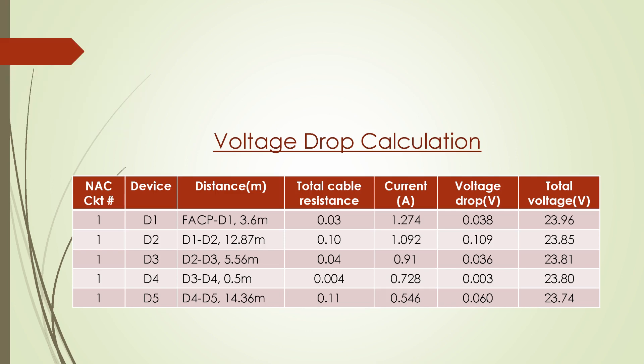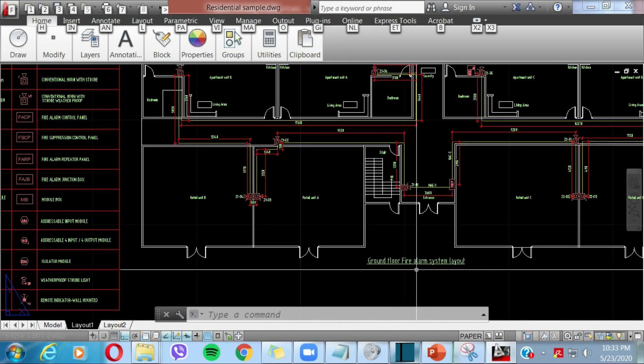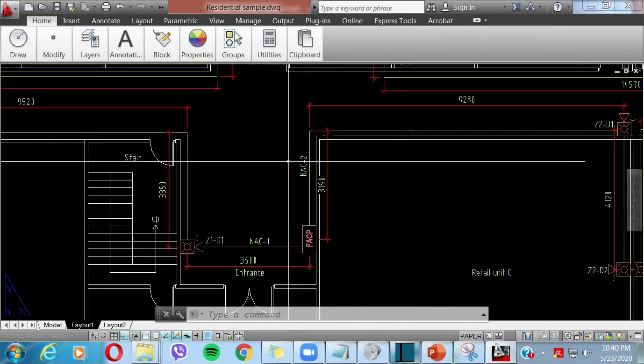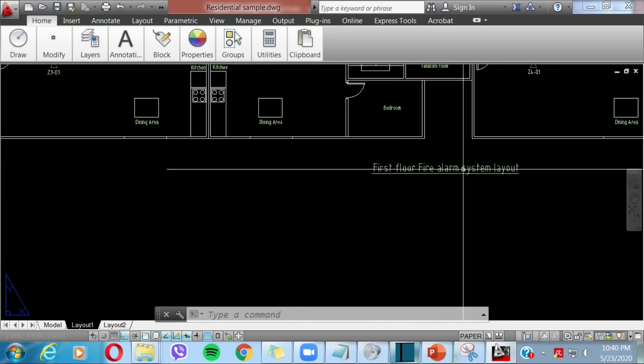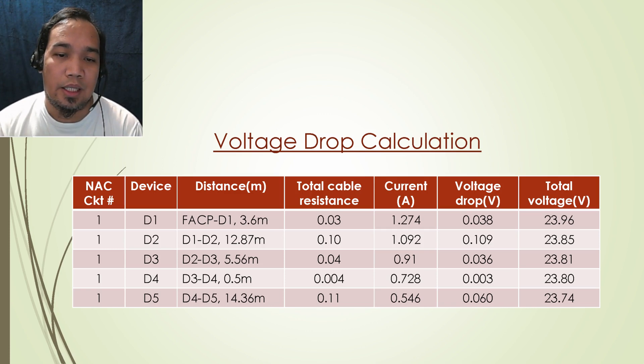I prepared a sample of fire alarm design for this tutorial. The type of occupancy is mixed occupancy. The building is residential G plus one floor with a retail unit at ground level. The design has four numbers of NAC or notification appliance circuit to cover the whole building. With instruction in step one to six which I discussed earlier, the details are summarized in table for NAC 1 and NAC 4 as example. NAC 2 to NAC 3 can be calculated as well in same procedure.